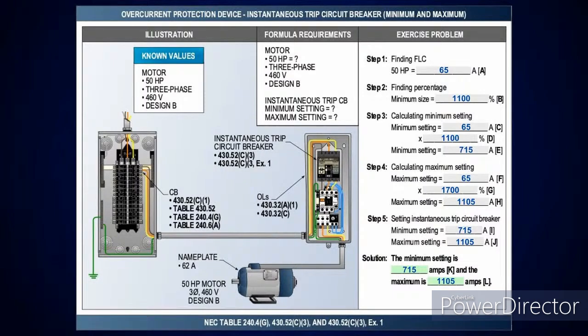So take 65 amps at 1700%. That's going to give you a maximum setting of 1,105 amps. Now, the point behind this is we're using the same type horsepower rated motor and all that. But what we're trying to point out here is it just comes down to this: you're still following the same type step-by-step method. You just have to find the percentage that's going to apply.